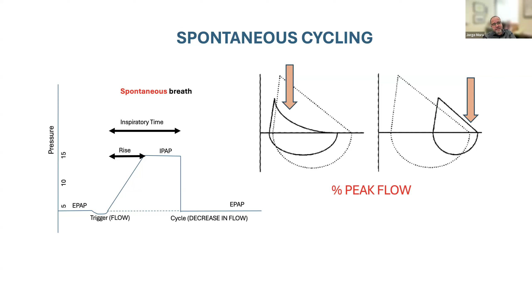And that is important because, in both respiratory assist devices and ventilators, you're able to adjust how easy it is for these devices to provide the pressure, based on the trigger effort and the negative pressure exerted, and how fast they will cycle when flow decreases. And that matters because, for example, in patients with COPD, you want them to have a harder time to actually trigger the device, because otherwise you can just start triggering one after the other and produce stacking of breaths. So you will use a less sensitive setting in these devices in patients with COPD.